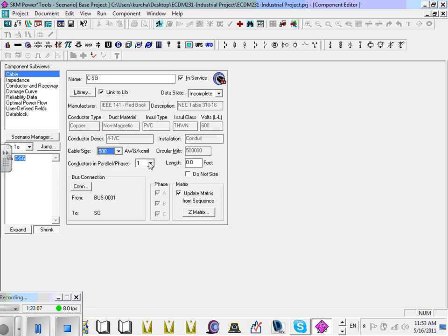And how many conduits do I run in parallel? I'm going to parallel 11 sets. I'm paralleling 11. Can you guys see conductors in each phase, 11? Remember, we're bringing the power to the service here. And how far?